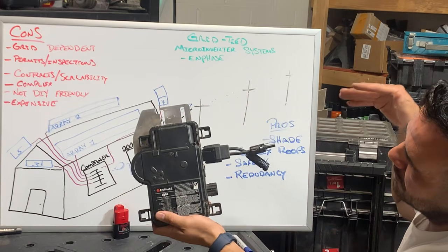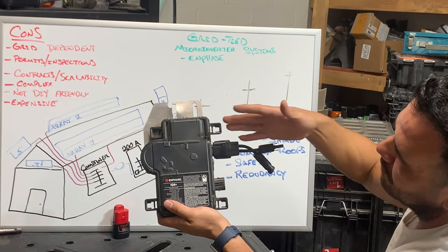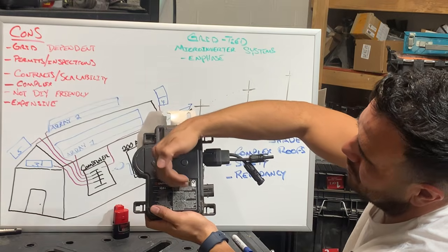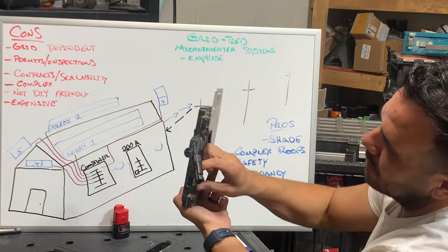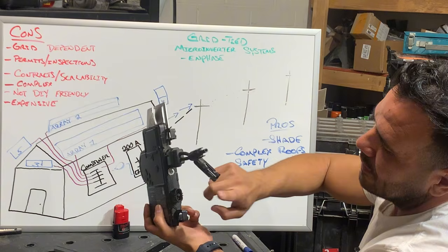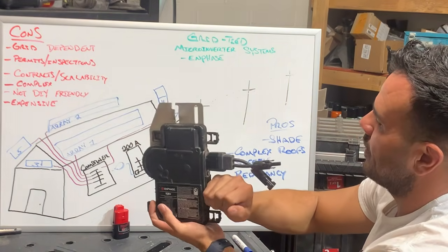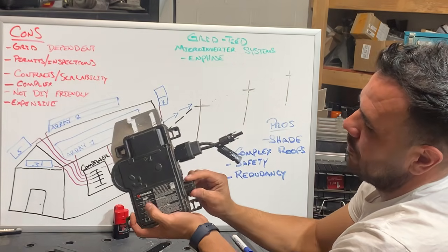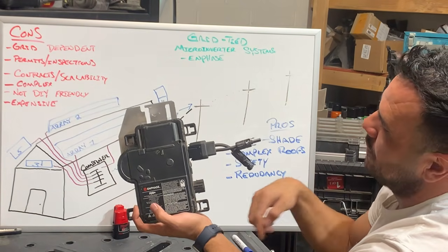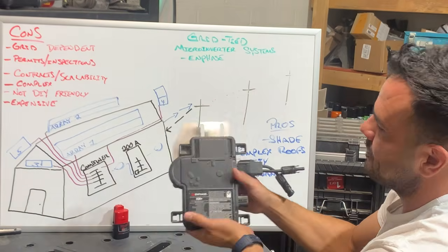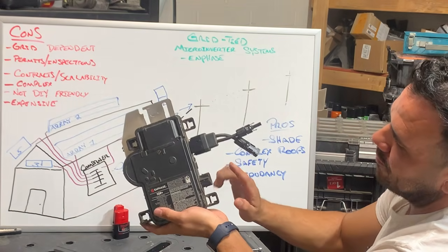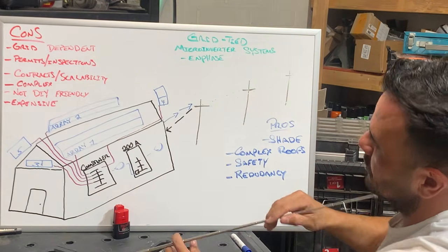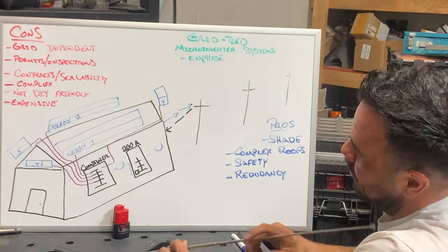So we would have DC power, or DC current, coming from our solar panels. Our microinverter converts that DC current to alternating current. And the alternating current comes right out of this little plug here. And this little plug has a branch connector, I think is what they call them. But it's just 2 wires that connect here, and they go to the next microinverter, which is then going to the next one and the next one. And eventually, at the end of this, you'll have 2 wires that will go to our combiner box. And so our combiner box is going to take the place of our string inverter.